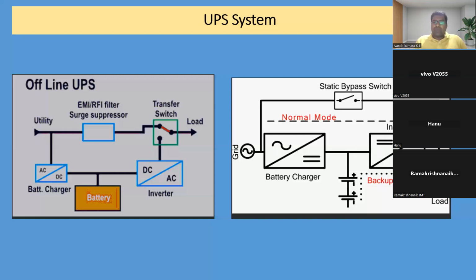Once backup is over, nothing will happen. It will go to bypass mode. Bypass is connected to grid power again. Generally, they will not advise connecting normal grid power to bypass, but sometimes it will connect. Otherwise, in case of a parallel configuration, it will go to the other UPS.